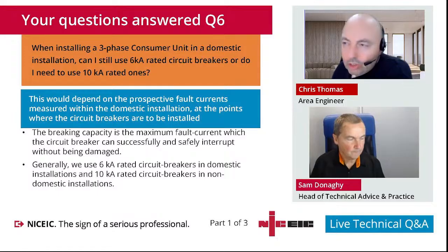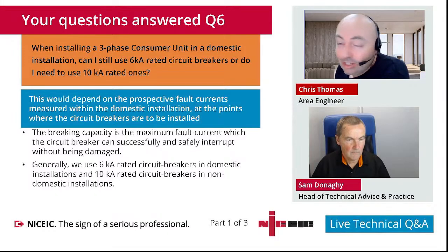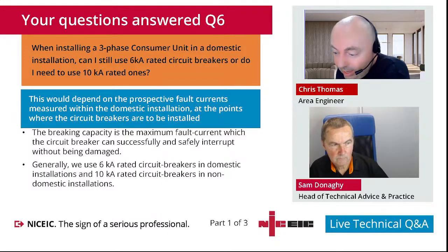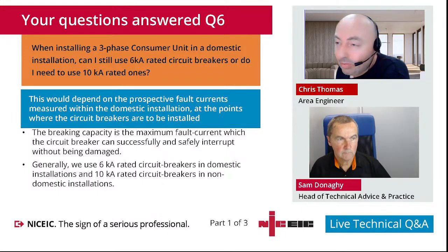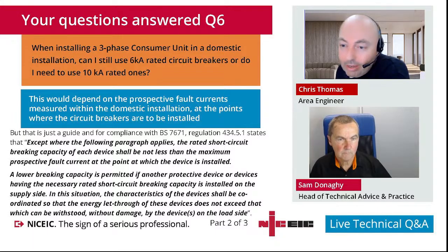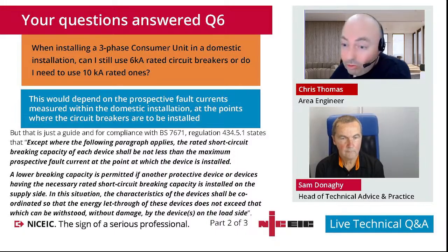The assumption would be if you're using three-phase that you might have to increase the breaking capacity of the breakers. It's not necessarily the case. It comes back to design analysis, or just looking at the design overall. Chapter 43, protection against fault currents, would be relevant here, because obviously we've got to make sure that any breaker which we size from a prospective fault current point of view is going to be suitable. So in other words, we need to determine what the fault current would be, and then make sure that the breaking capacity of the breaker is able to handle that safely.